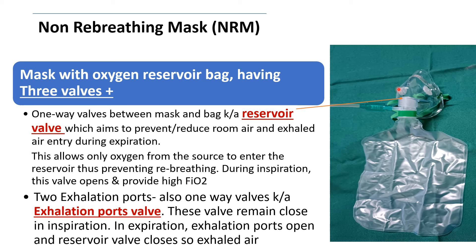The mask also has two exhalation ports, each containing a one-way valve. These exhalation port valves remain closed during inspiration so room air cannot enter the mask, allowing high oxygen concentration to be delivered to the patient. During expiration, the exhalation port valves open and the reservoir valve closes, so exhaled air exits into the environment.